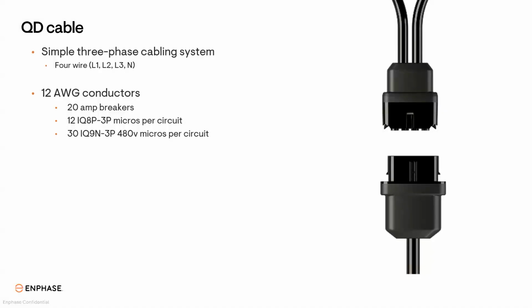These circuits, whether you're using an IQ8P or IQ9N, will land on a 20 amp 3-pole breaker of your voltage choice. If you're using the IQ9N, you're going to use 480 volts for the 3P, or for the IQ8P 3P, 208 volts. And again, you can only put 12 micros on an IQ8P 3P circuit per 20 amp breaker, and you can do up to 30 IQ9N 3P micros on a 20 amp circuit.